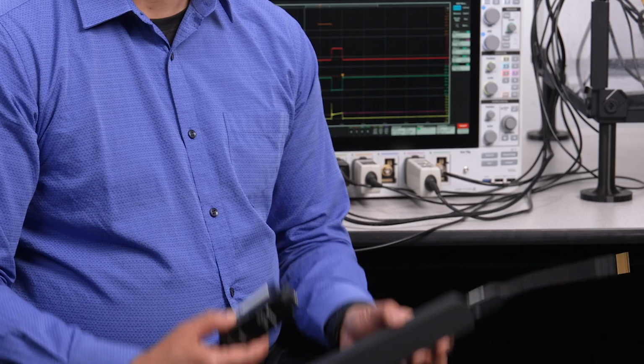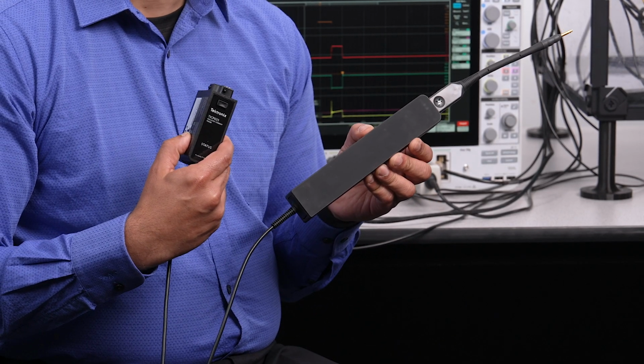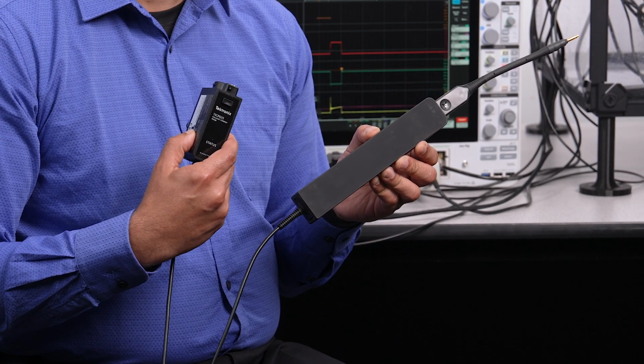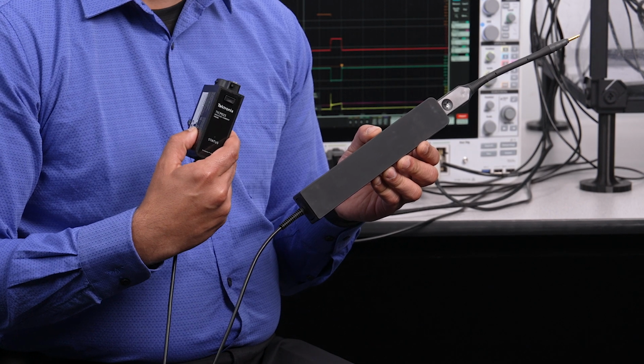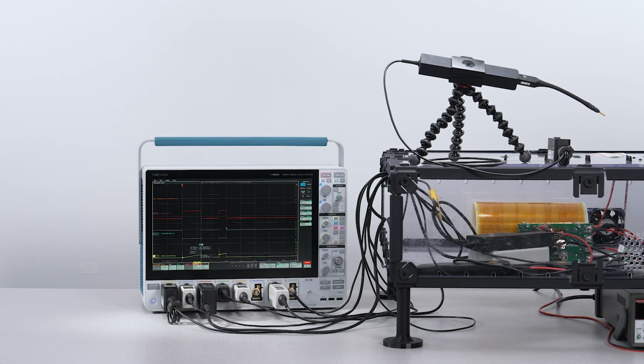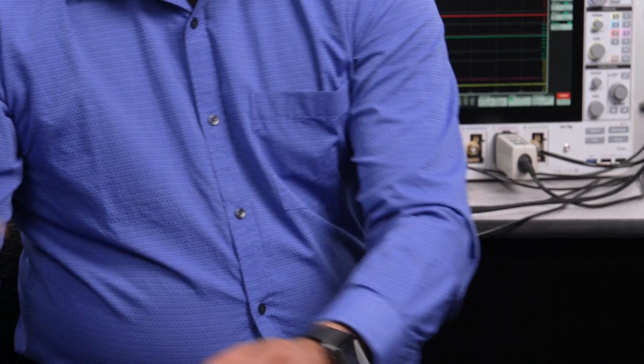The Tektronix innovative TICP series IsoVu isolated current probes are specifically designed for making a wide range of current shunt measurements with high bandwidth and low noise. They can make measurements from microamps to hundreds of amps depending on the connected shunt. Unique RF isolation helps protect the equipment and personnel from high voltages and enables outstanding common mode noise rejection.